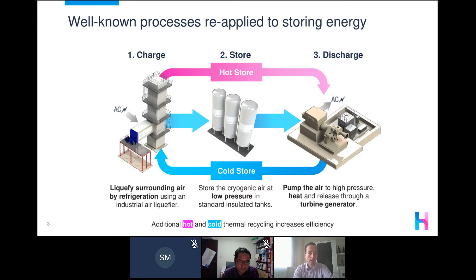On top of being a storage system - a large battery, a gigantic battery - it has multiple rotating systems: a generator, a steam turbine, and multiple compressors during compression and liquefaction. So it provides mechanical inertia, rotating inertia to the grid, which creates synchronous compensation, reactive power, and fast fault current infeed. In a way, this technology gives the same services you get from a fossil fuel plant, but without fossil fuel, without emissions.